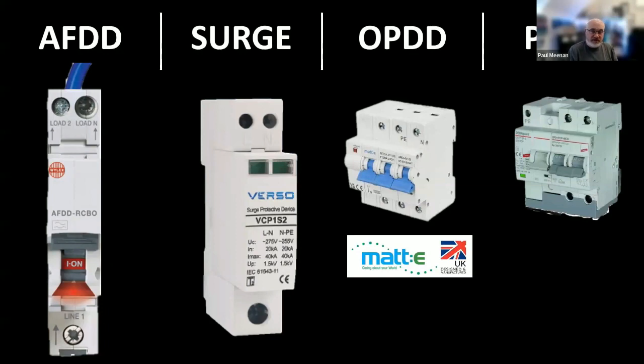But when we're on that journey of selection and erection of our protective devices, we're now in a world in England where we have an arc fault detection device to BS EN 62606. We have surge protection to protect against atmospheric strikes and strokes. Strikes being a direct strike, stroke being the after effect, where you could get transients of thousands of volts. And we then do staged protection to ensure that any voltage spike within the installation dissipates and is protected and connected to earth.